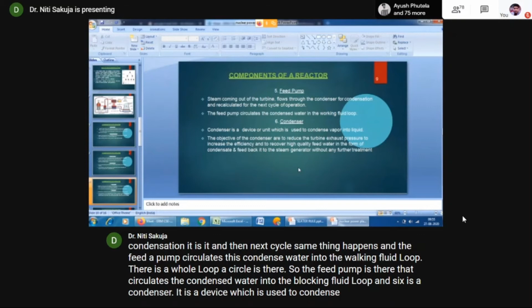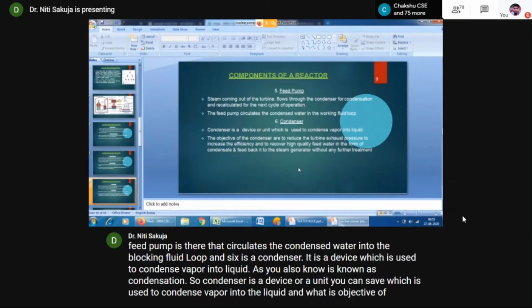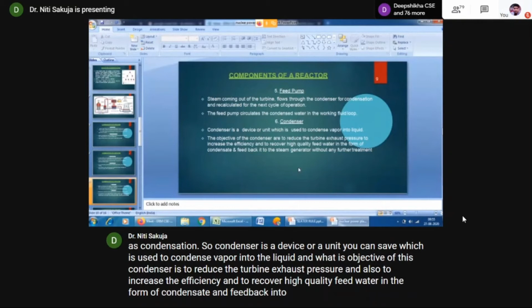Sixth is the condenser, a device used to condense vapor into liquid, also known as condensation. The objective of the condenser is to reduce the turbine exhaust pressure, increase efficiency, and recover high quality feed water in the form of condensate, feeding it back to the steam generator without any further treatment.